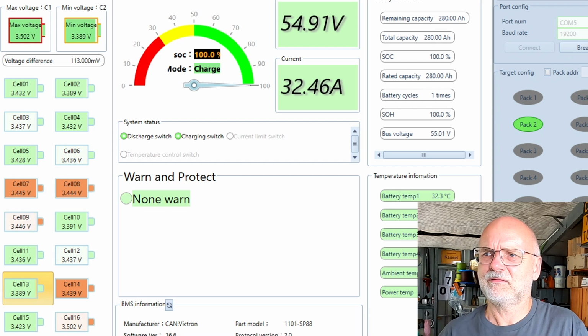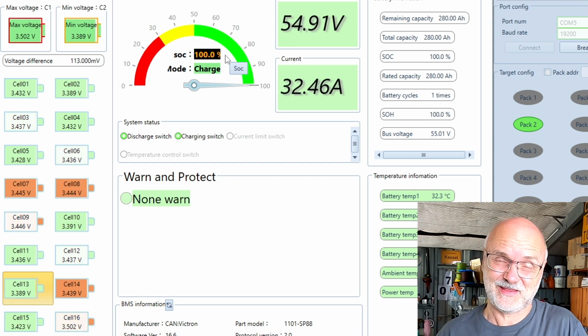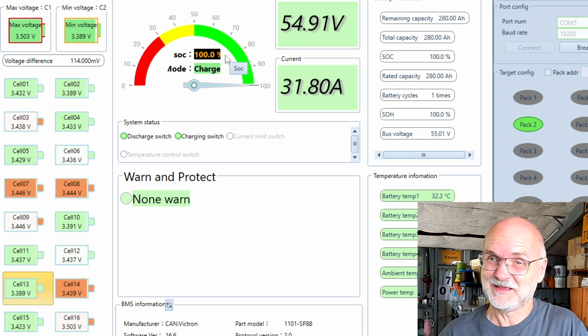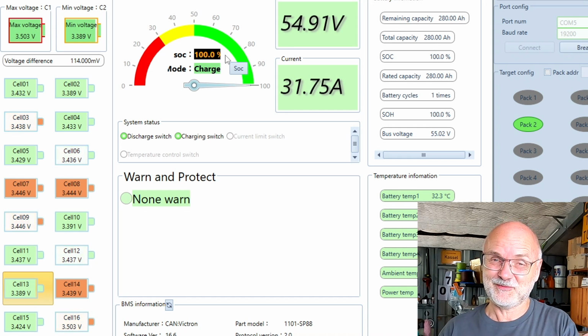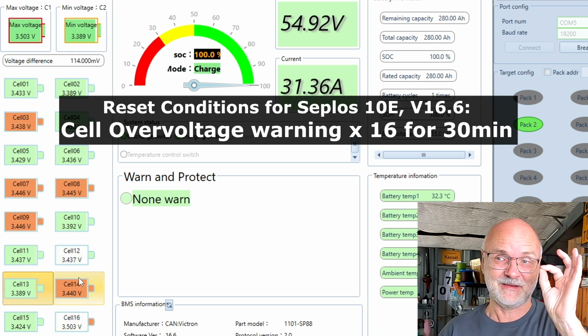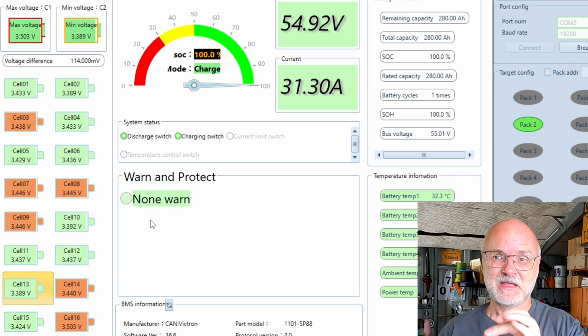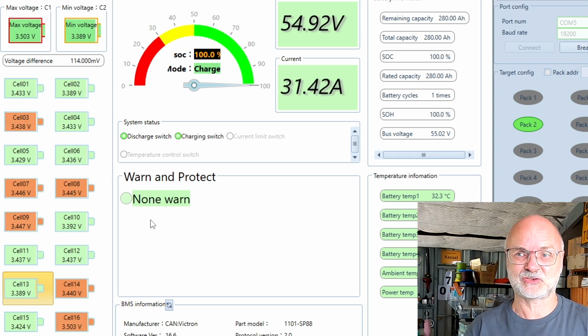Okay, after another half an hour or so, the BMS has actually reset to 100% state of charge. Look at this. So it worked with this BMS - if you are over a certain voltage for half an hour, it resets to 100%, even though we have not reached any over voltage protection. No pack voltage protection, nothing.